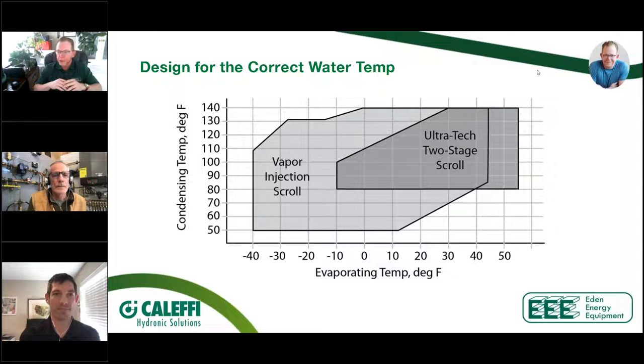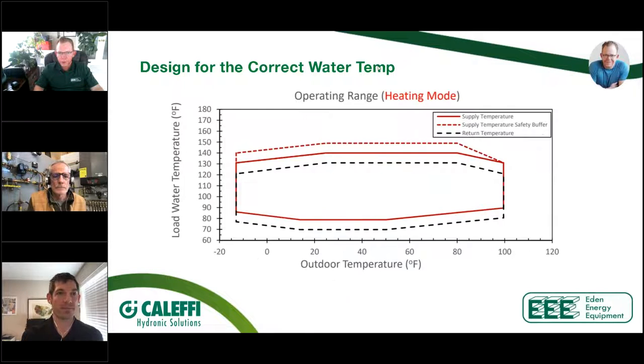And frankly, Bob would tell you, and so would Max, the same applies with a boiler. Yeah. If we had a boiler that was just sat on low fire and ran all the time, we wouldn't care. If it's on high fire running all the time, we know you've got a problem. But low modulation is really critical in this equipment and very important.